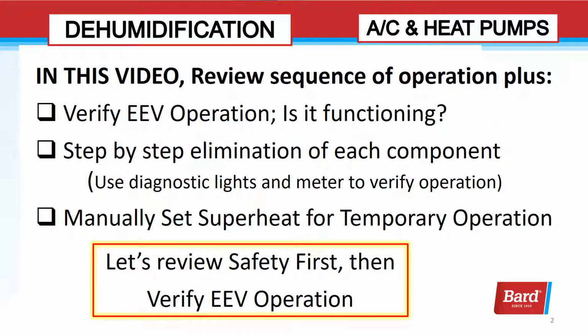In this video, we'll review the sequence of operation, verify how it's functioning, and how to reclaim refrigerant from a unit with this valve. Step-by-step elimination of each component using diagnostic lights and a meter to verify the operation. And last, we'll learn how to manually set superheat up for temporary operation in case you need to order a part. Let's start by reviewing safety first, and then we'll verify the EEV sequence of operation.